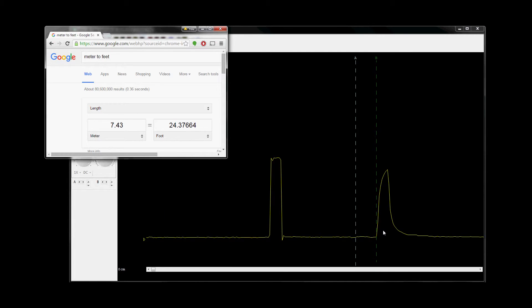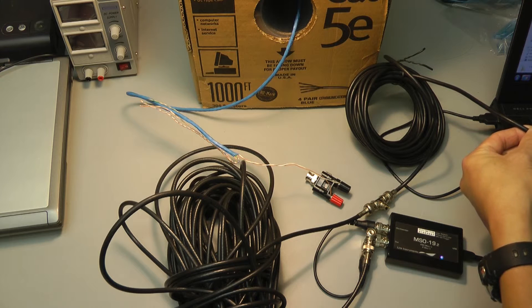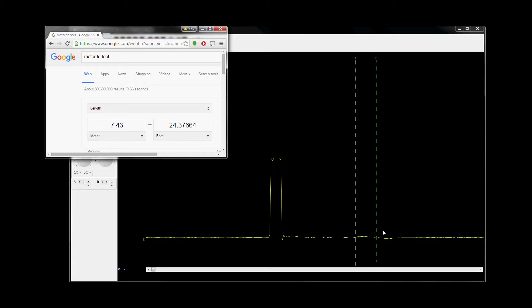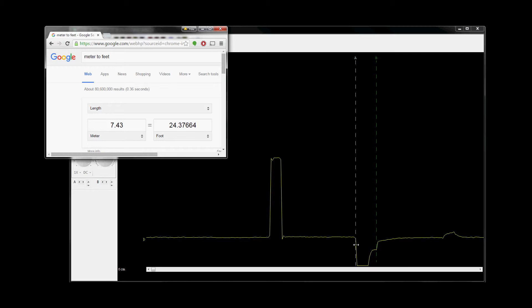Now I added a terminator to the end — it's gone. But if I short it out again, the mismatch is happening here. I get the short to ground. You can also use this to detect if you have a break in your cable — short it together or short it to the shield. The reflection gives me the total length, so I can actually use this to measure how long the cable is and where the break is.